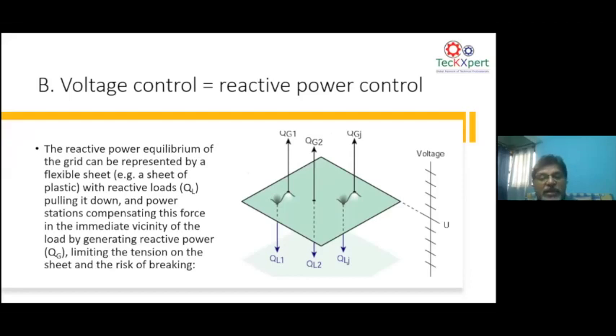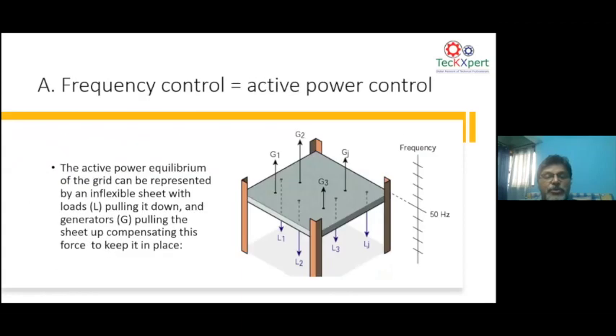As I said before, when it comes to reactive power, locally we try to compensate the reactive power where there is a need to pump in reactive power to stabilize voltage. So the whole concept of reactive power control to manage voltage, and the whole concept of controlling frequency by keeping the power consumed and generated equal, is how the grid is controlled.